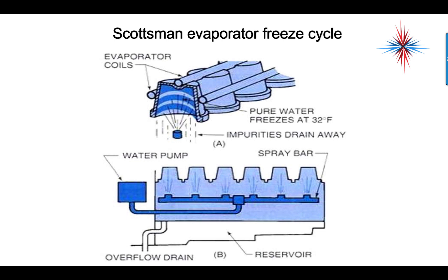Scotsman does things a little bit different. The plates in a Scotsman machine are a lot of times horizontal. The spray bar sprays up into a little cup. That cup is the evaporator because the evaporator coils are connected directly to it. So the impurities do not stay - they're heavier, they'll fall out and back into the reservoir. During the freeze cycle, this evaporator bar sprays up.